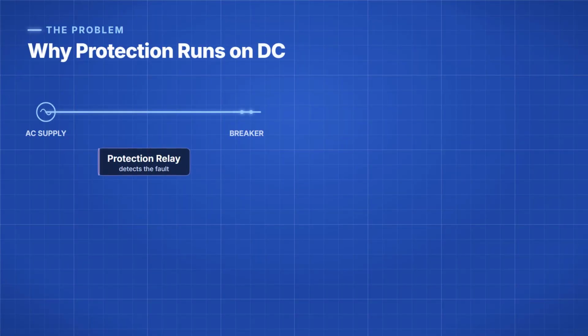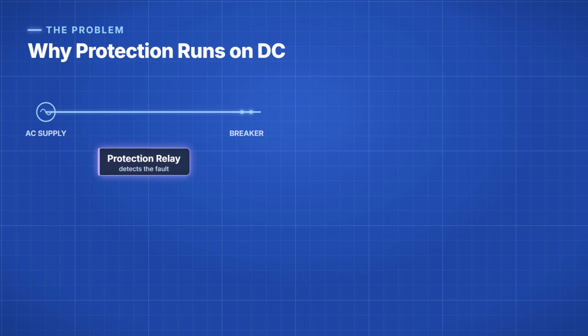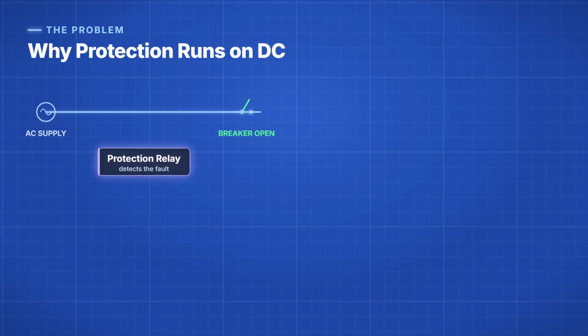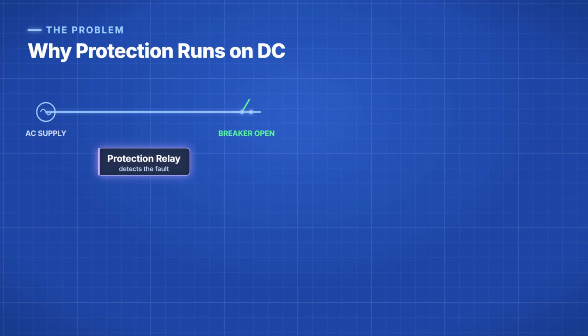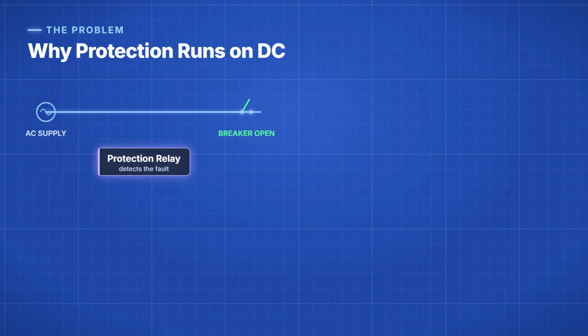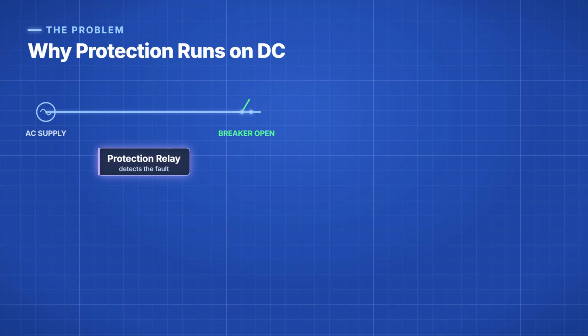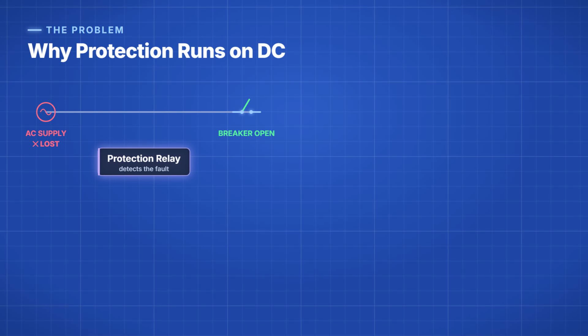Let's start with the problem the battery bank is there to solve. When a fault hits the network, a protection relay has to detect it and tell a circuit breaker to open, which clears the fault before it can damage equipment. But opening that breaker takes energy, and the fault has often weakened or knocked out the local supply at the same time. So the substation can't trust its alternating current supply to be there when it's needed most.